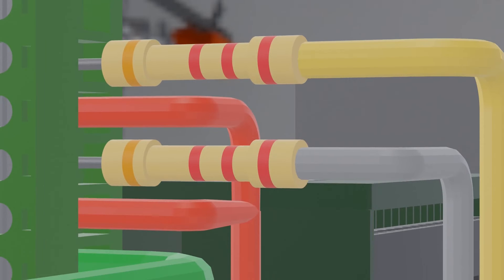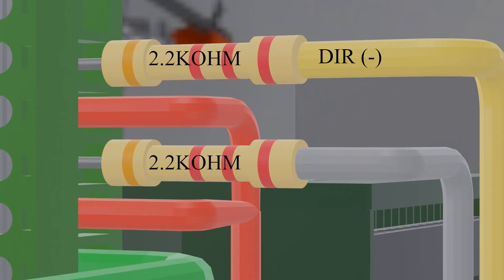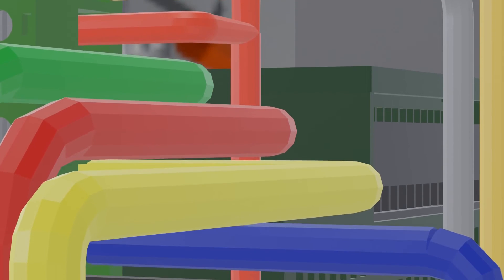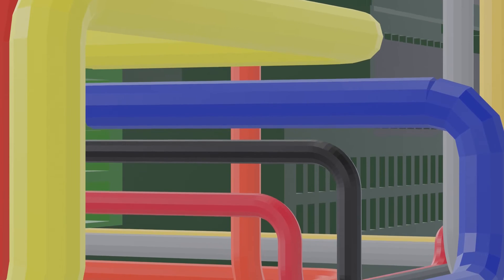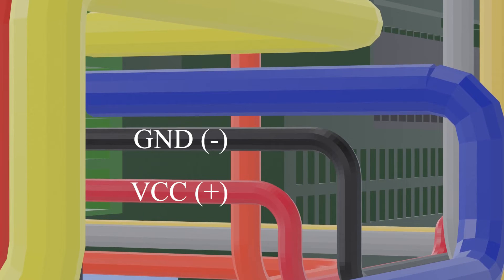Now we will see the connections of the pulse and direction. We have two resistors of 2.2 kΩ, medium watt, connected to the negative direction and negative pulse. On the other hand, we have the positive direction and positive pulse together, which connect to the positive supply of the PLC. Then we have the four motor signals: B negative, B positive, A negative, and A positive, and the 24-volt supply GND negative and VCC positive.